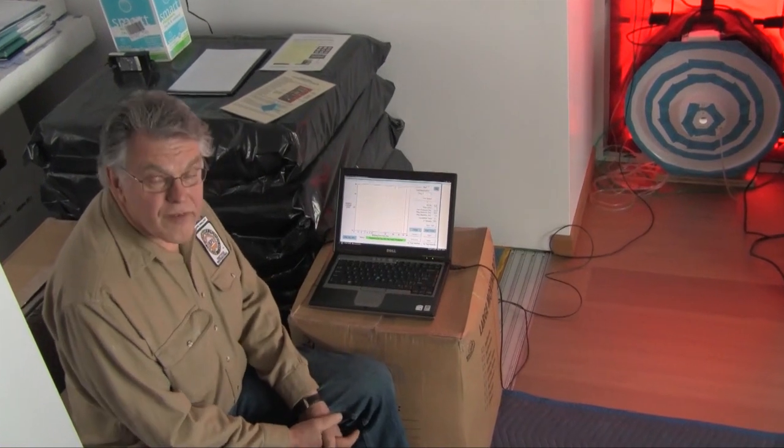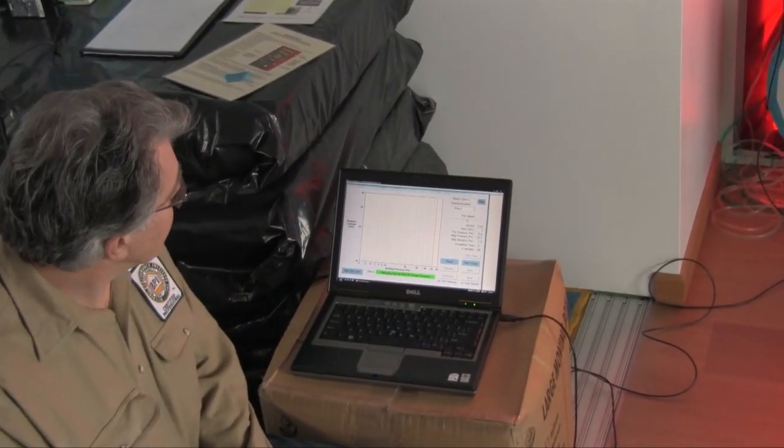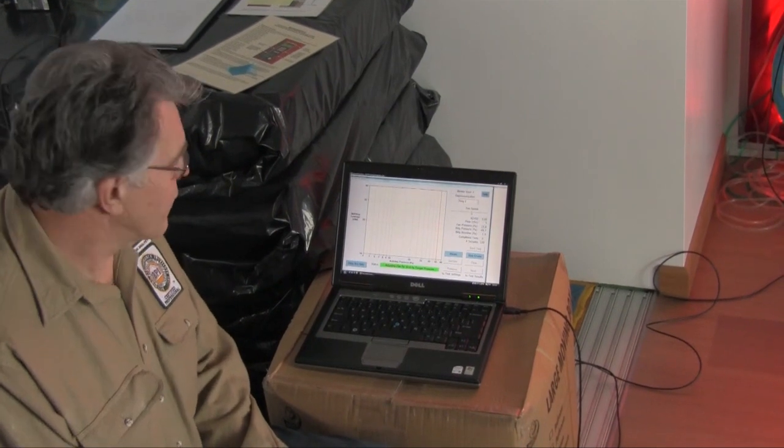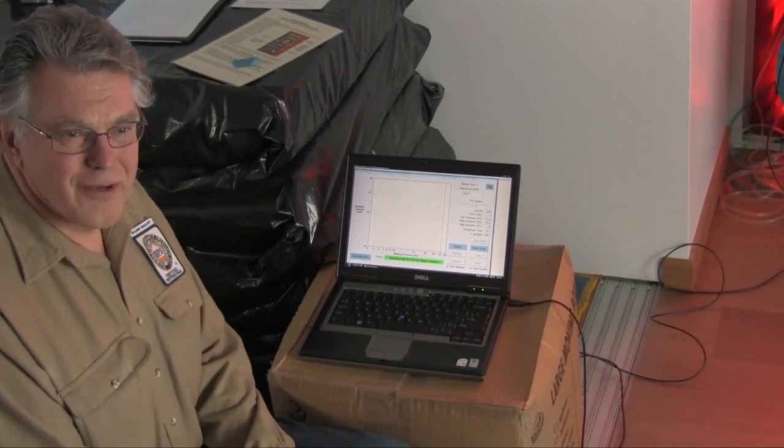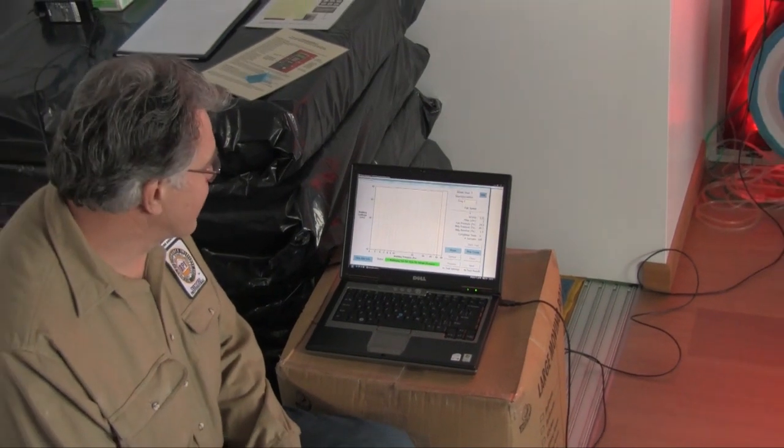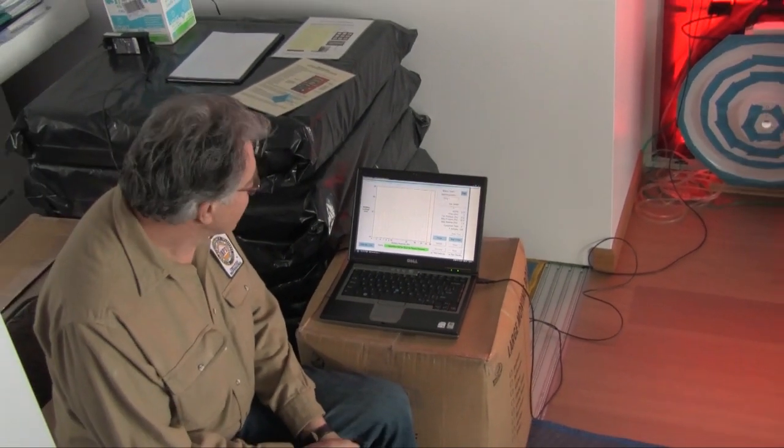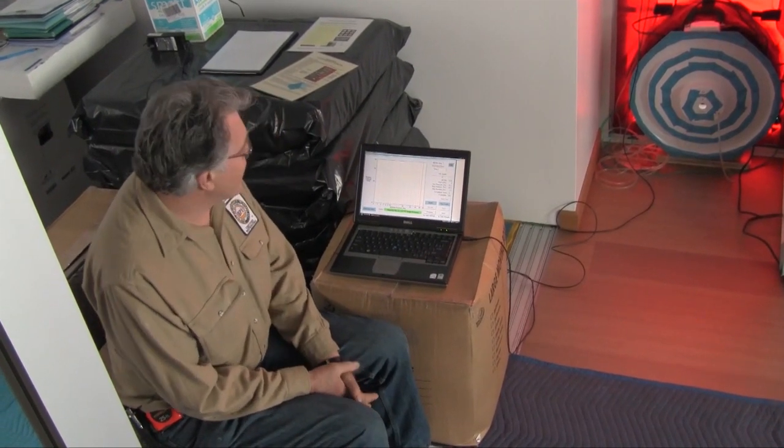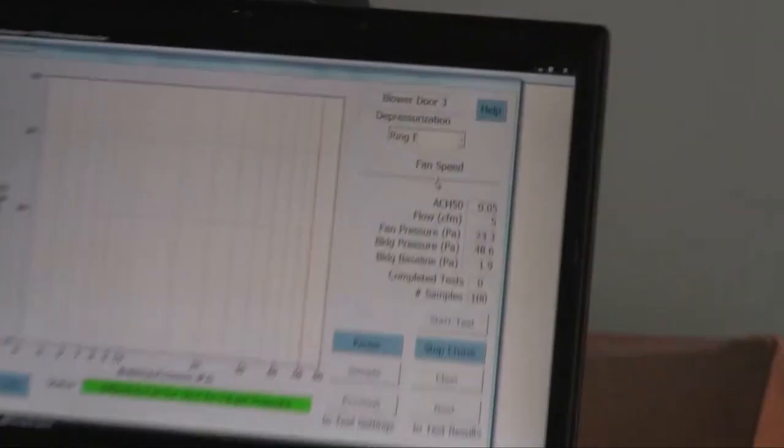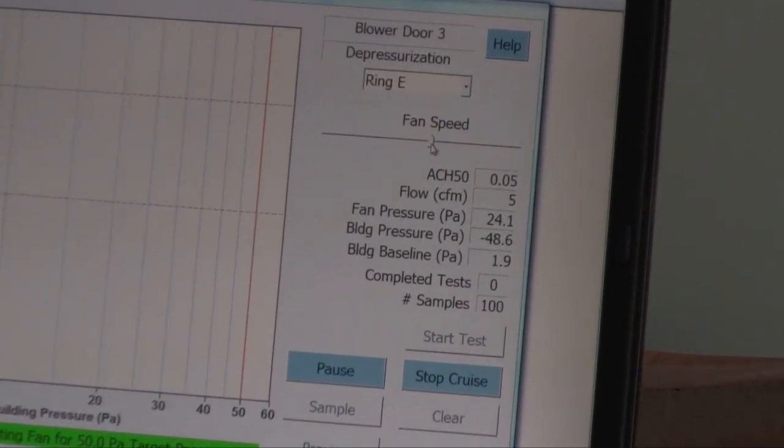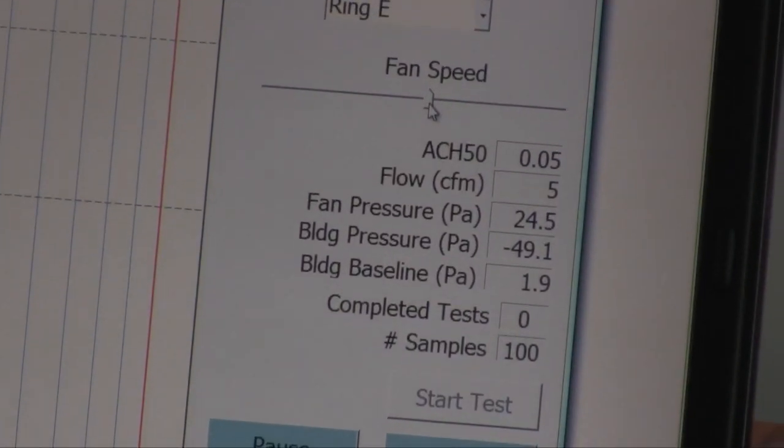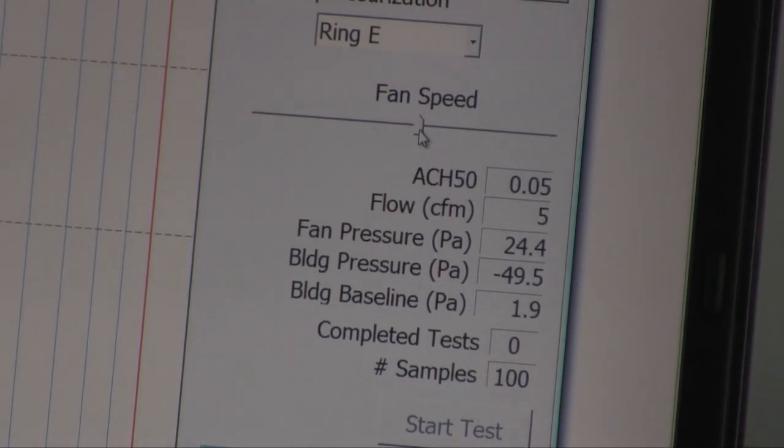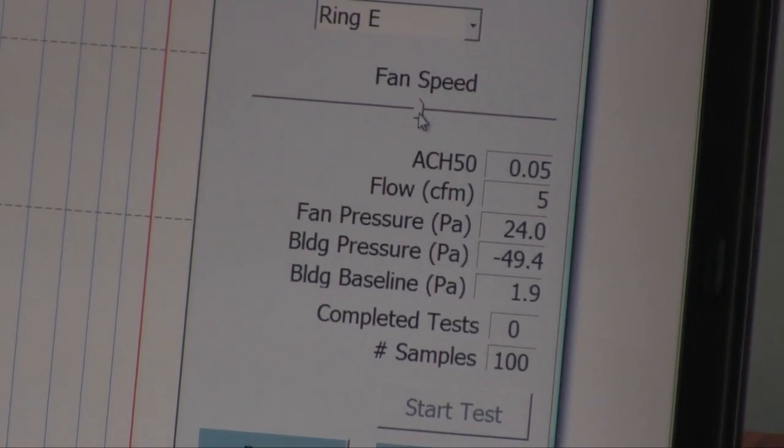Our air changes per hour at 50 pascals is calculated at 0.05. That is phenomenally low. Tom, I knew you did a fantastic job in sealing this house, but I don't know how you got it that tight. It's way, way tighter than anything I've ever tested before. In fact, I don't think I've tested anything below 0.5, much less 0.05.